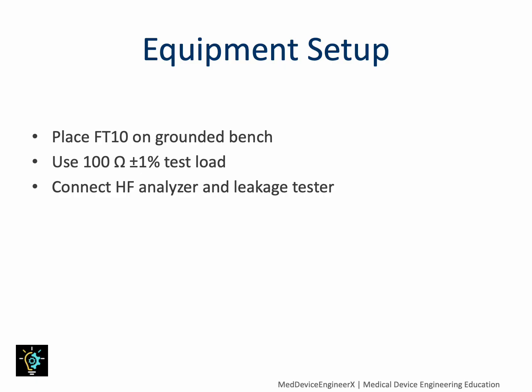Testing begins with proper setup. Place the FT10 on a grounded static safe bench. Attach a calibrated 100 ohm load to the output port. This simulates surgical conditions. Connect a high-frequency analyzer to measure output power and a leakage tester to assess electrical safety. Confirm all instruments are within calibration date. Setup accuracy is critical because the data you gather depends entirely on stable connections and reliable reference equipment.